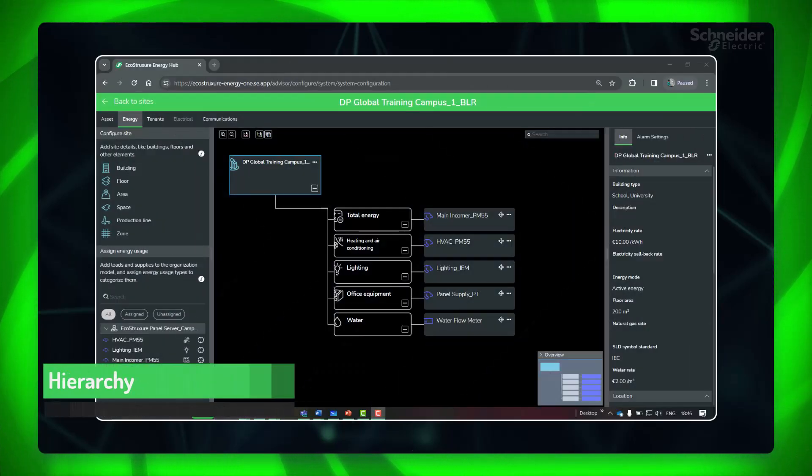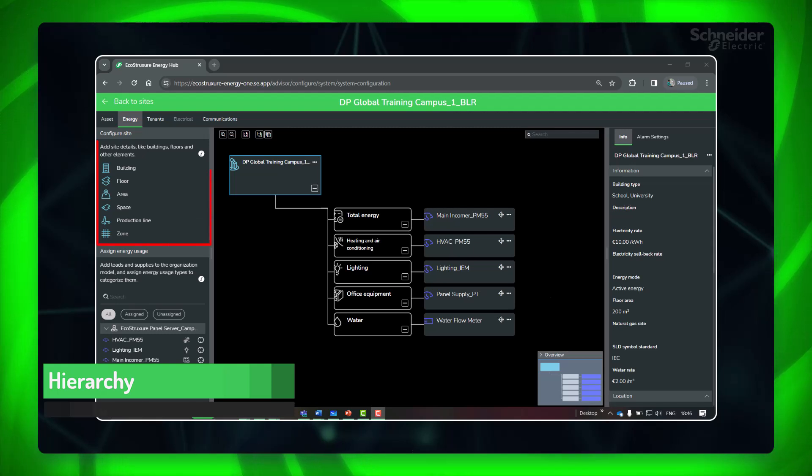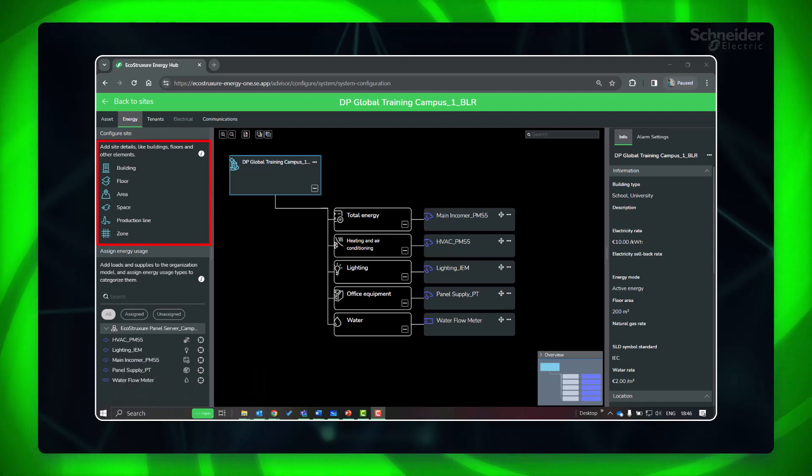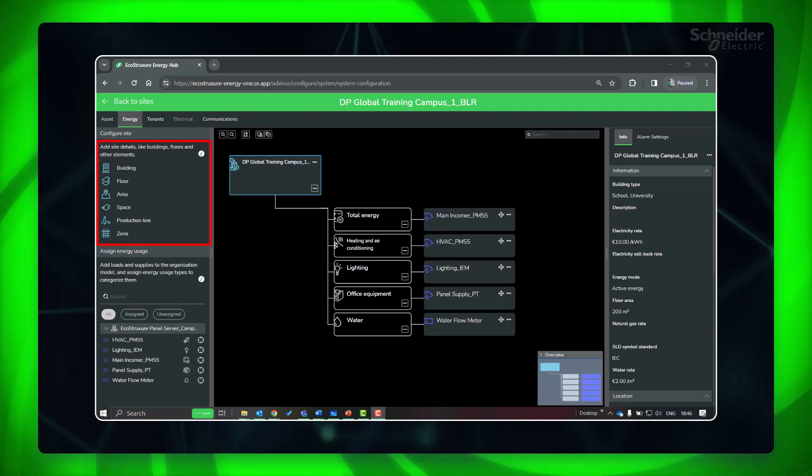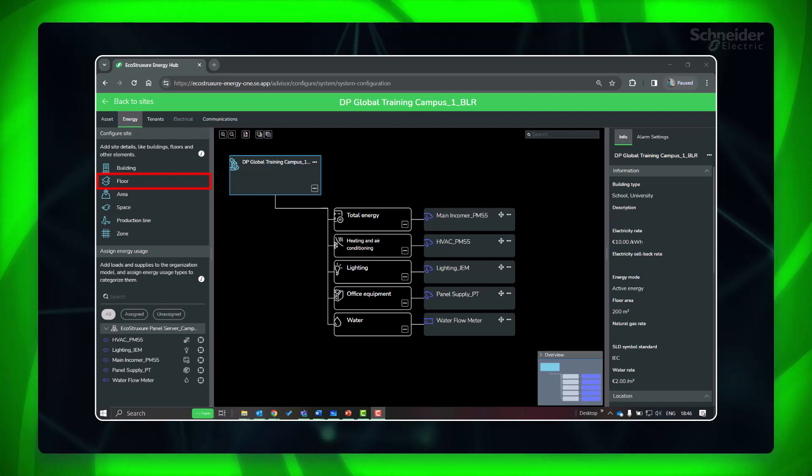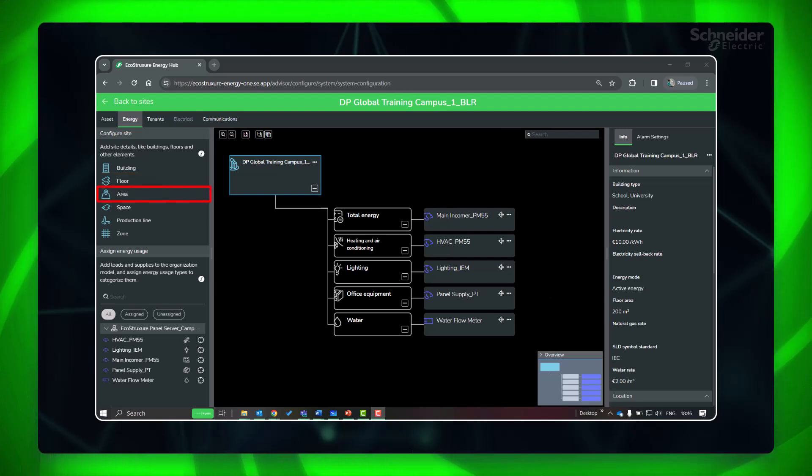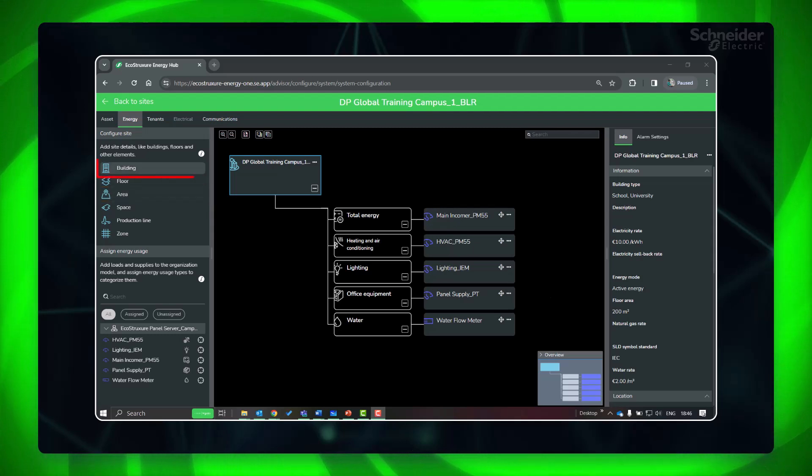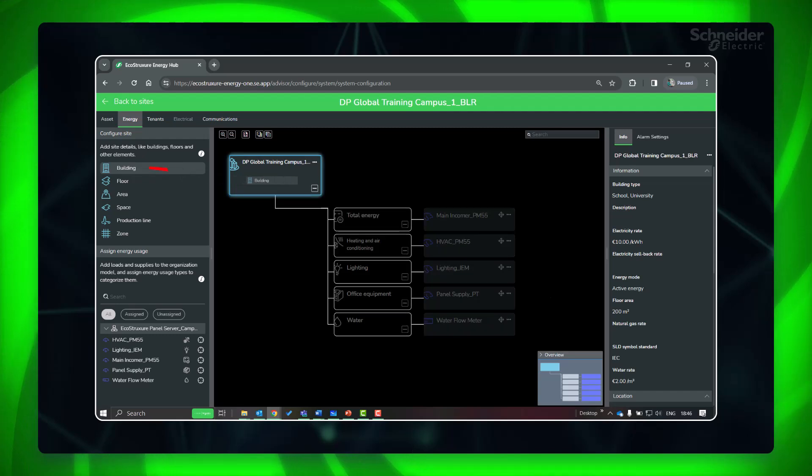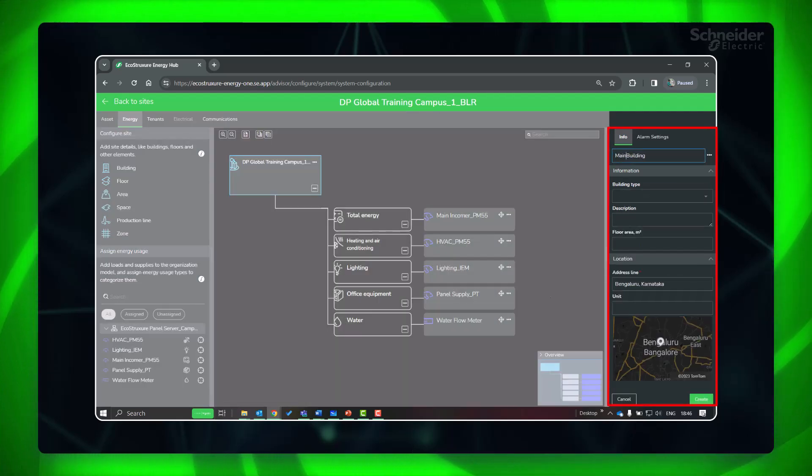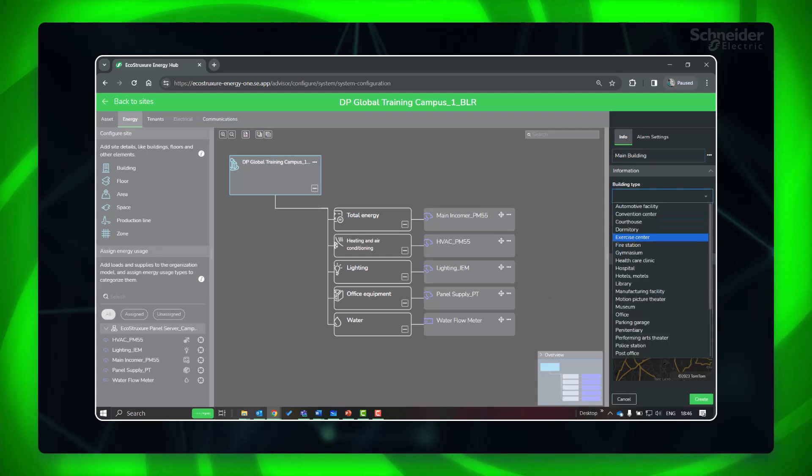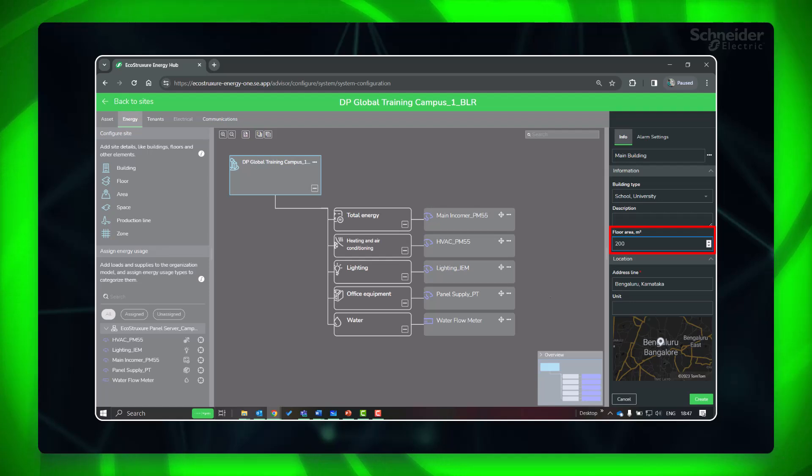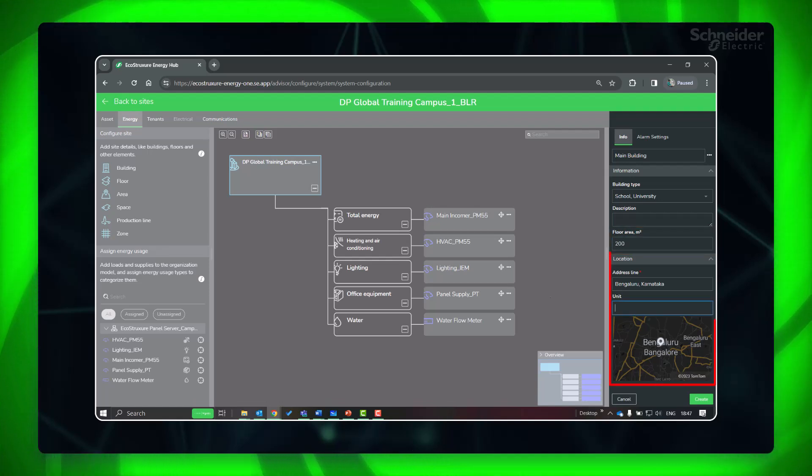Let's build the hierarchy of this site by adding the elements like buildings, floors, etc., as per the location of the energy consumed or generated. In this site we are monitoring loads in one of the floors of the main building. This floor has two areas, namely office area and lab area. First, let's add the building. Drag and drop the element to the site. Fill in the details of the building in the info panel. Floor area and location are required for getting correct data in energy dashboards.